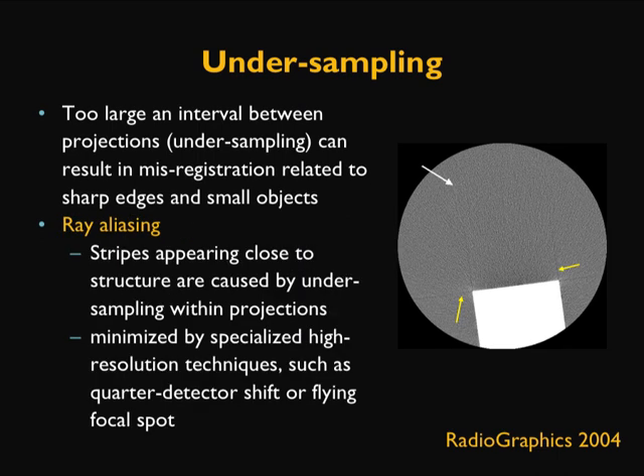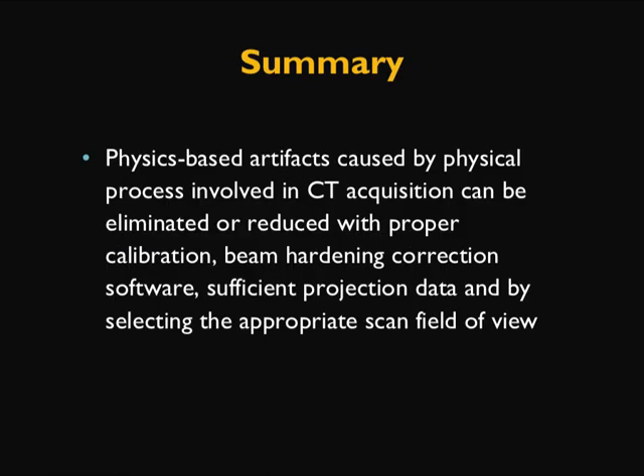Under the same category of under-sampling, there is also ray aliasing. Stripes appearing close to the structure are caused by under-sampling within the projection, as shown by the yellow arrows. This is minimized by specialized high spatial resolution techniques such as quarter detector shift or flying focal spot. In summary, physics-based artifacts are caused by physical processes involved in CT acquisition and can largely be eliminated or reduced with proper calibration, beam hardening correction software, sufficient projection data, and by selecting the appropriate scan field of view.